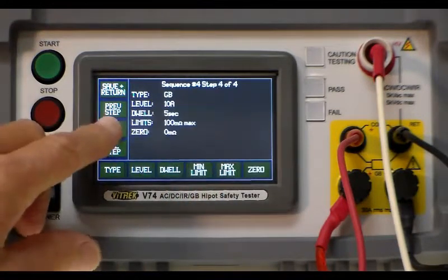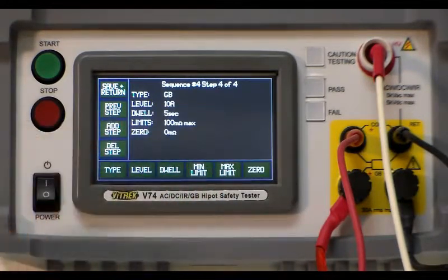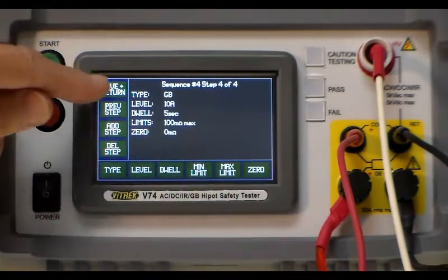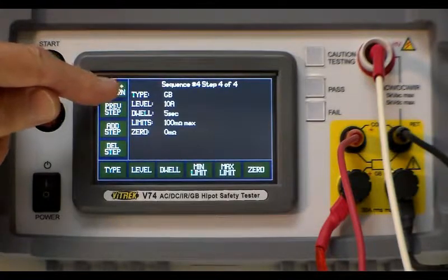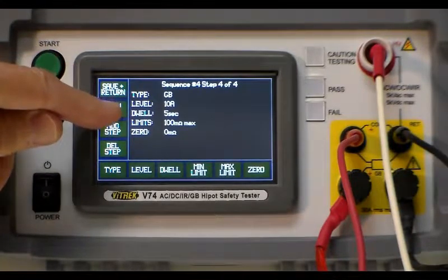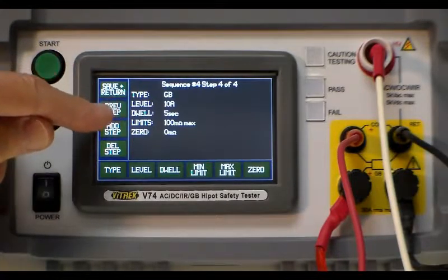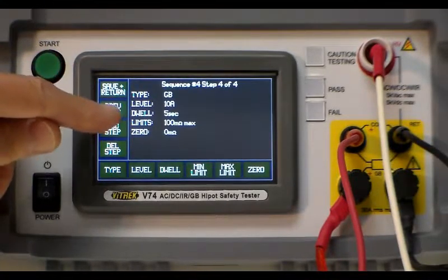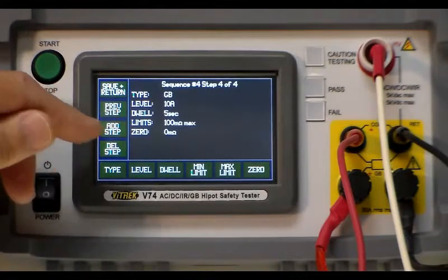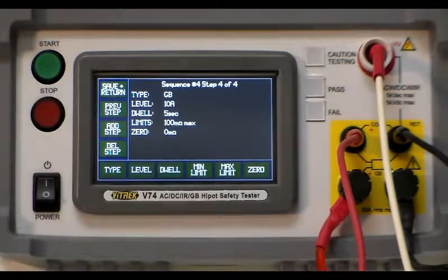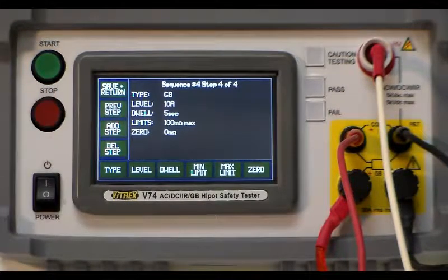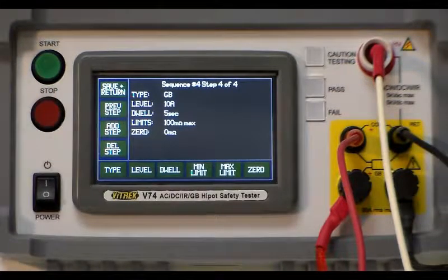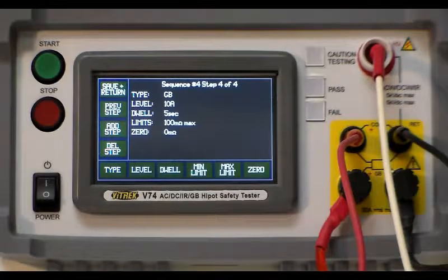The next step would be the ground bond. In this case we're doing a ground bond at 10 amps dwell for five seconds. Your maximum ohms would be 100 milli ohms and zero would be the minimum.